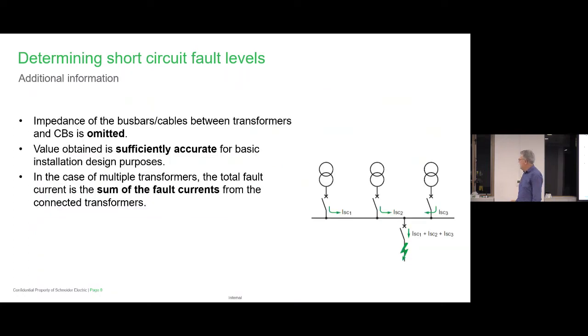So this area here is really just showing you that we've only got one MVA on the previous one, but here we've got three transformers, all connected. And each one of those has a circuit breaker on it, and that circuit breaker there has to withstand the potential of this, the fault level of that transformer. But if we have three of them, this circuit breaker has to be the sum of all of them. So we're looking at a sizable fault level that is on this board if you've got that many.